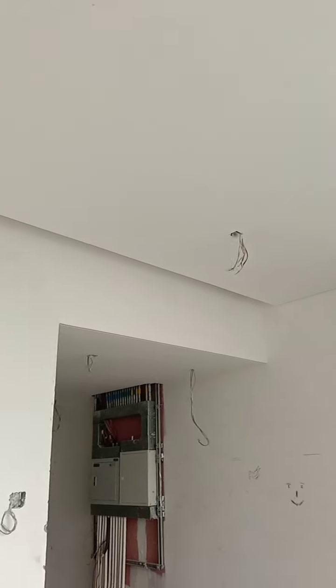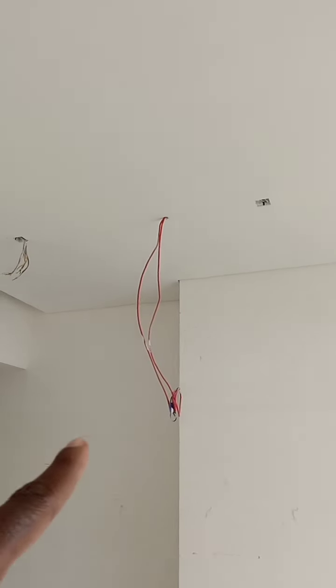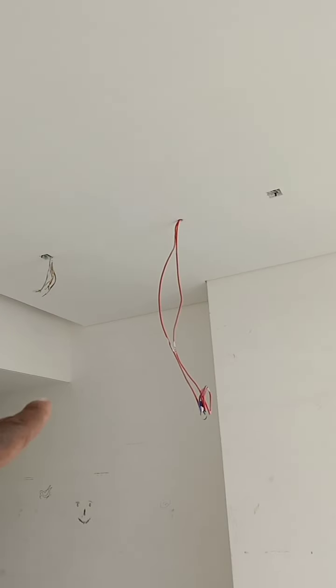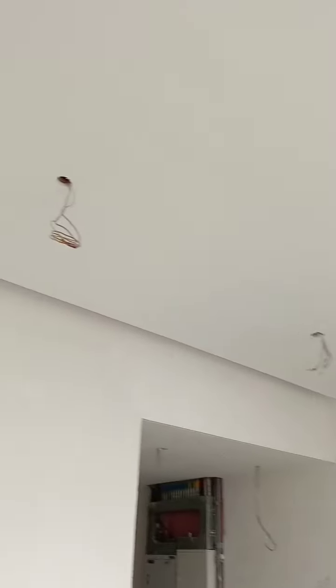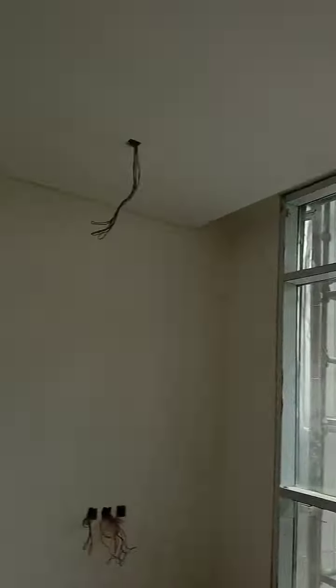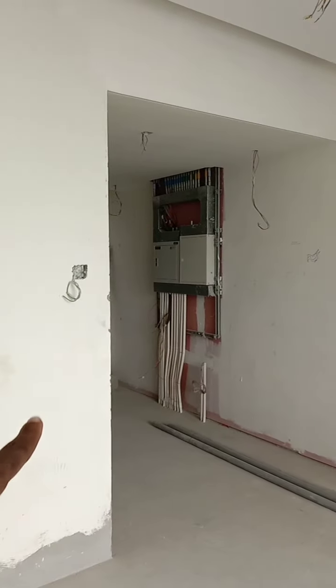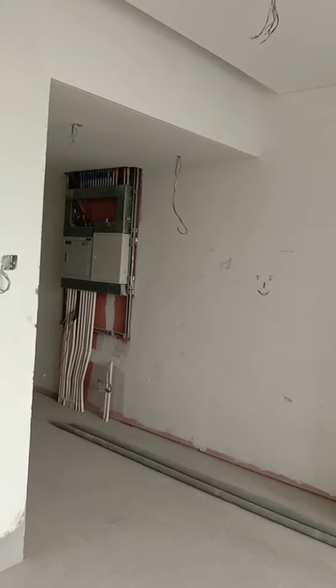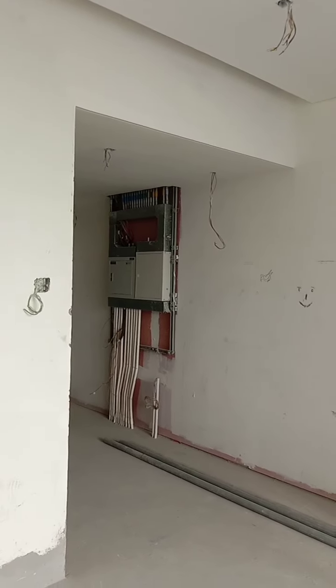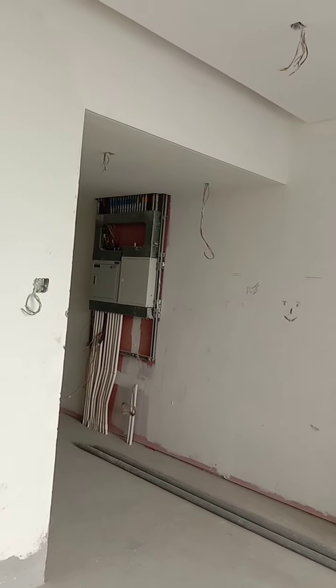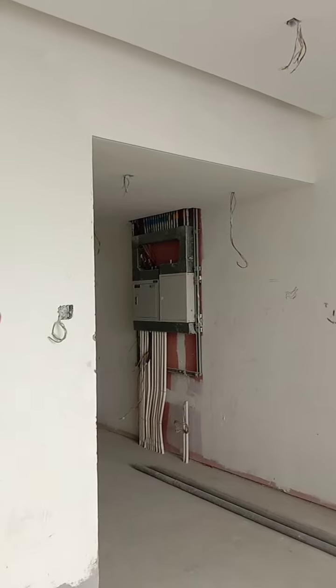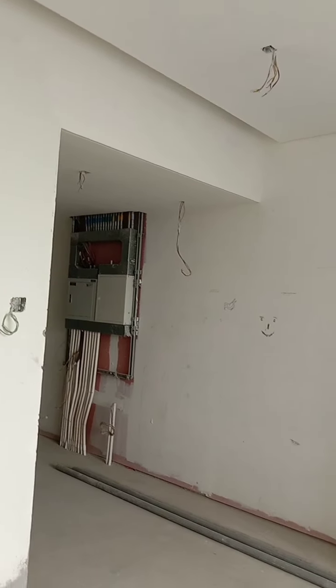Next, we've also done the cable and the wire pulling. As you can see, this is the fire alarm cable, which is done, which is the FP200. We have the PVC cables also, PVC wires as well, which are pulled, as you can see. And then we have our DB installation, which is done as well. You see right down, we have some PVC conduits, which are also installed and then connected to the trunking, which we move now to our panel board or our distribution board, which is the DB.